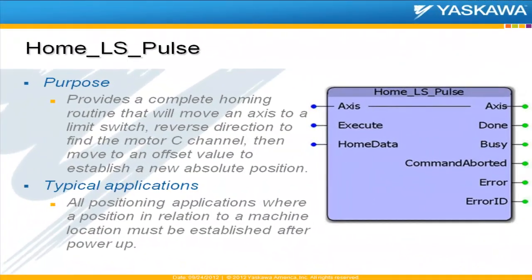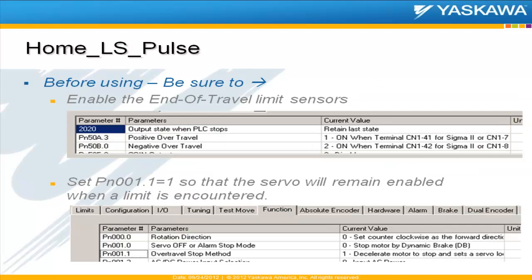We'll move on to the home LS pulse block, and it's a fairly straightforward procedure here. It provides a complete homing routine — it'll move an axis to a limit switch, reverse direction, find the motor C channel, and then move to an offset value and establish a new position. Even applications that use an absolute encoder need some sort of reference routine like this.